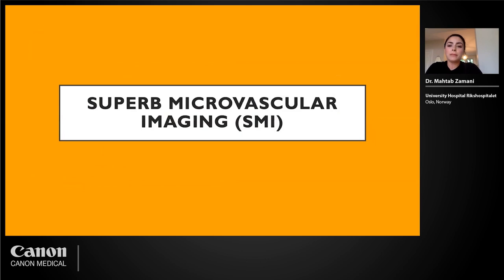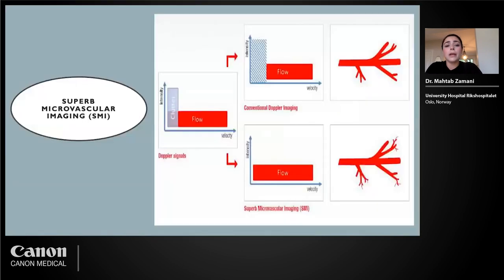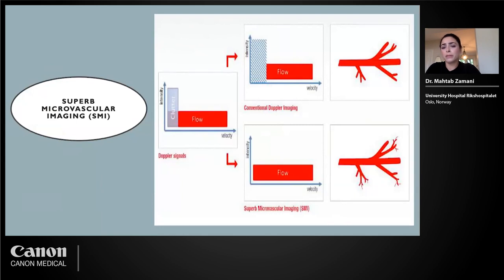Superb Microvascular Imaging (SMI) is a new method developed to overcome the limitations of conventional Doppler. It uses an exclusive algorithm — software on a normal Doppler machine — which successfully removes artifact and clutter arising from nearby structures while at the same time preserving the microvasculature. This is visible in comparison images: whereas conventional Doppler cannot show this microvasculature or low-velocity blood flow seen in intraplaque neovascularization, SMI clearly reveals it.